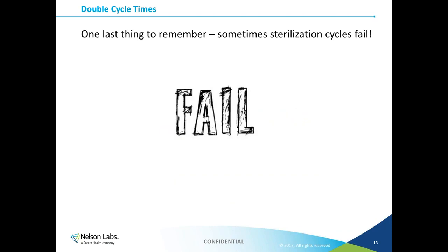One last thing to remember: sometimes sterilization cycles fail. As one EO consultant once said, it is not a matter of if this is going to happen, but when. It is of the utmost importance to design and validate packaging and product which can handle twice the exposure to EO as necessary. If the first cycle fails, there must be a validation in place showing it is acceptable to re-sterilize the product. If this is not in place, the entire load of product must be thrown away — potentially a huge sum of money. This applies to all forms of sterilization, not just EO.